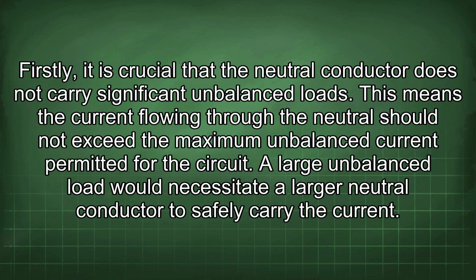Firstly, it is crucial that the neutral conductor does not carry significant unbalanced loads. This means the current flowing through the neutral should not exceed the maximum unbalanced current permitted for the circuit. A large unbalanced load would necessitate a larger neutral conductor to safely carry the current.